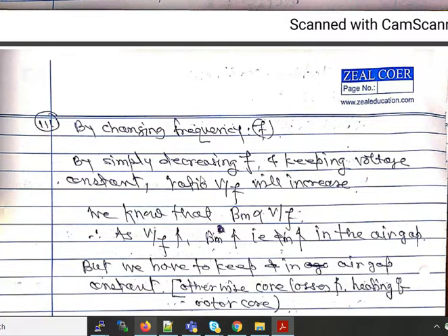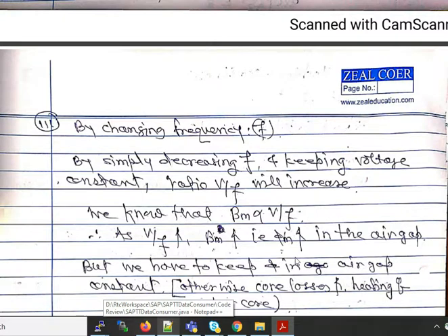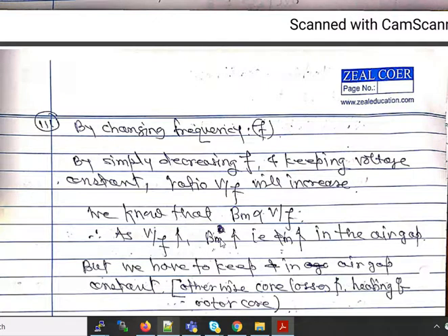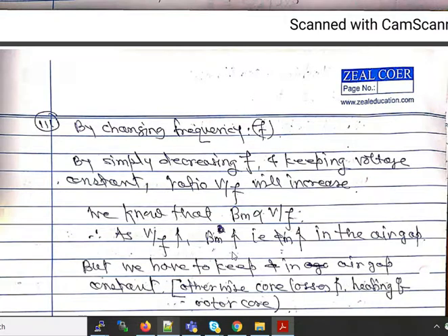Now consider speed control by changing the supply frequency. By simply decreasing the frequency while keeping voltage constant, the V/f ratio increases. Since maximum flux density Bm is directly proportional to V/f, as V/f increases, Bm increases — that is, the air gap flux increases. We must keep the flux constant because increased Bm raises core losses: hysteresis loss is proportional to Bm^1.6 and eddy current loss is proportional to Bm², which overheats the motor.